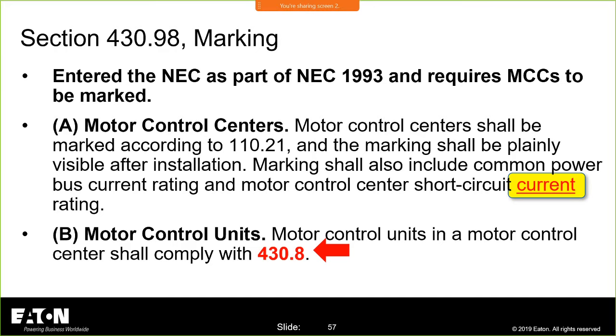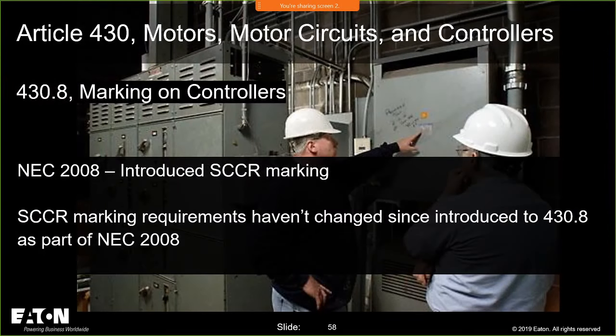But it does cause us to go back and review that motor control centers, those buckets, motor control units, all of that has to be applied correctly with regard to the available fault current. They'll have the withstand capabilities rated, and they'll tell you how many cycles that equipment is rated for. So if you have a short time delay breaker upstream, you've got to make sure that you clear that fault fast enough to stay within the ratings of that equipment. And again, the 2008 edition introduced the marking of the short circuit current rating, and then the 2017 edition introduced the requirement to have the available fault current.